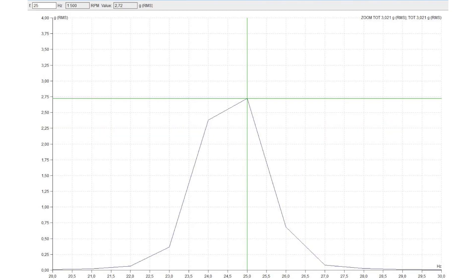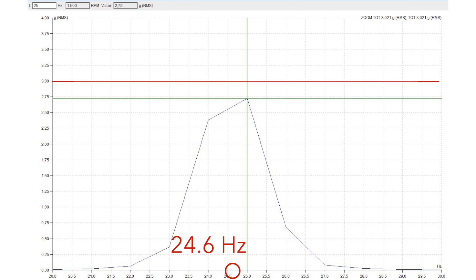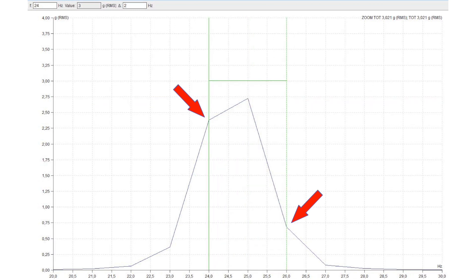What about the amplitude? We set the signal generator to 300 mV RMS on frequency 24.6 Hz. In the instrument we set the sensitivity to 100 mV per G, meaning we expect the value 3 G on 24.6 Hz. If we look only at the peak, it is not correct — the value is only 2.7 G. The reason is that the energy is also in the sidebands, and for a correct result we need to include the sideband amplitudes. The best way is to use the delta cursor, which shows the correct RMS value.